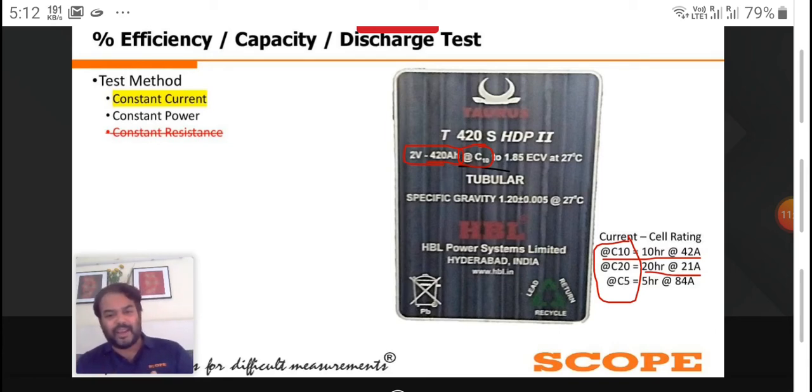Let's say manufacturer A makes a 2-volt battery. Though it is 2 volt, the actual components and design are different from manufacturer B of the same specification. Manufacturer B will have another set of data, because the design and other things are different. As you have experienced already, one manufacturer's cell of the same rating looks different from another manufacturer's. So each manufacturer has to give the limits specific to that cell or battery.